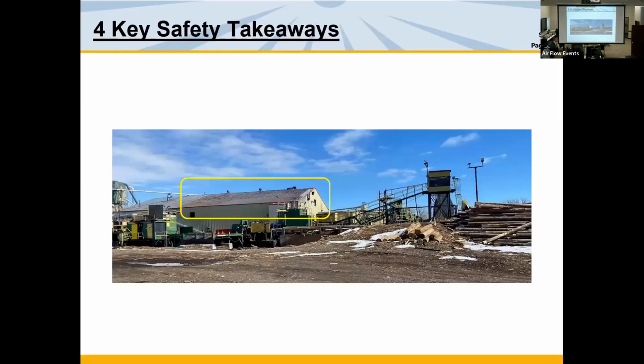Next slide. All right, that's where I was in Montana. It was a mill where they make lumber, okay? Acres and acres and acres of cut down trees, and they had a fire, all right? And you can see the roof all discolored from the fire that happened. And this was ironically with a unit heater that we just sold about a month ago and had been in service for 3 days. So how does a brand new unit heater in service for 3 days take the whole mill out? Sad part about it was it was the 3rd fire they had in 10 months, and it put them out of business. So 85 people lost their jobs.